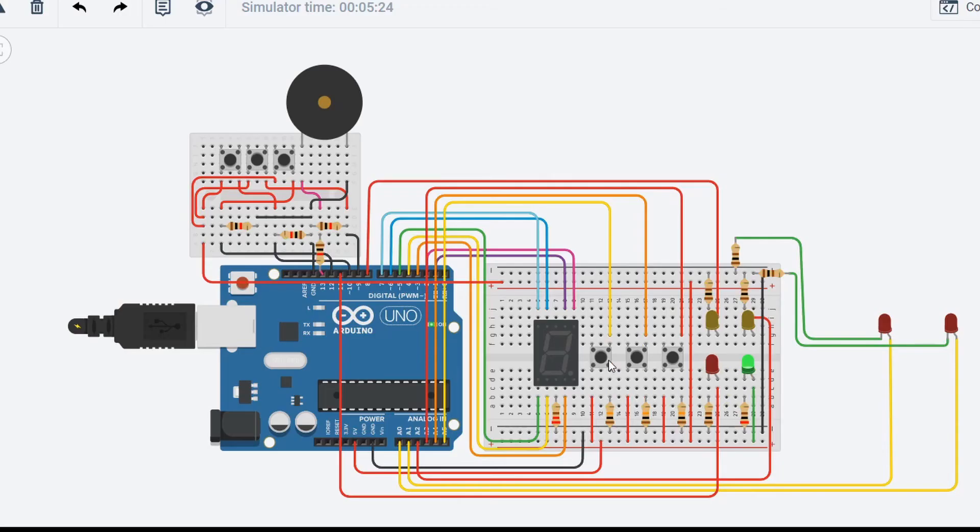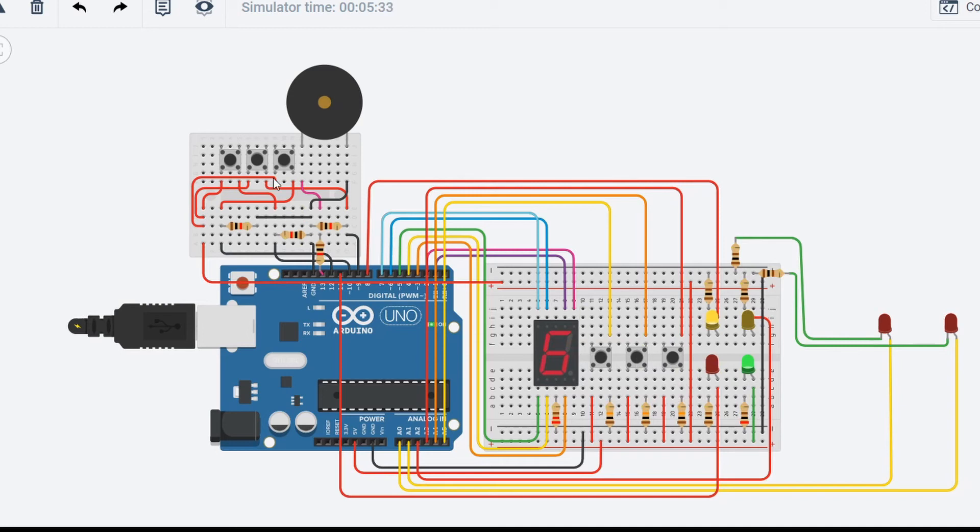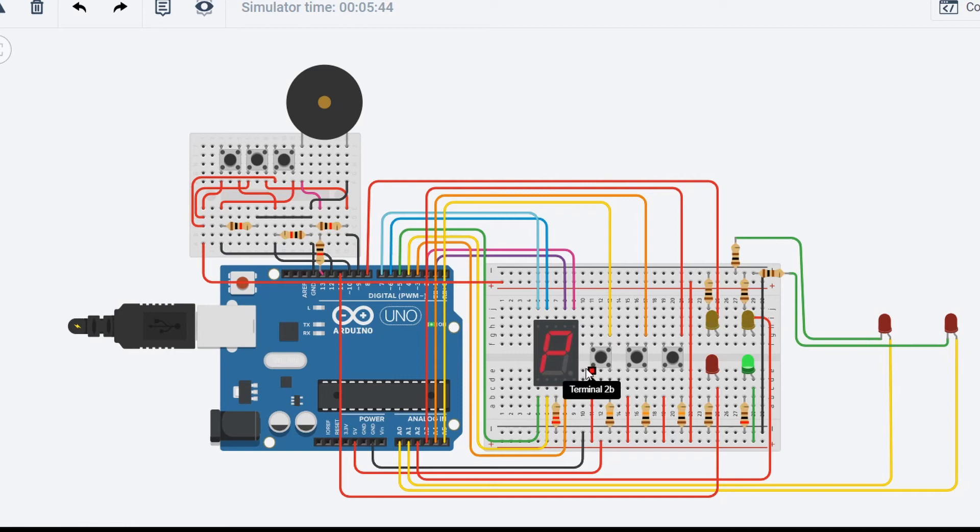Now, some of the other options I wired for my personal use is if I go to coding option six, this is test mode. So this will make it if the alarm goes off, the horns will not sound at all, just the strobes will turn on. And I coded this to do a system trouble, which is shown as a P for problem because I can't do T with a seven-segment display.